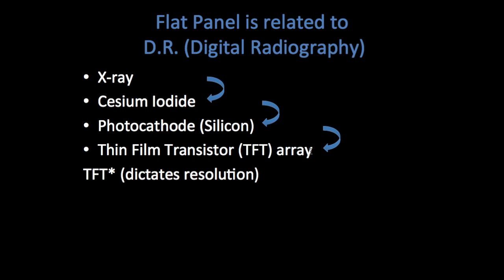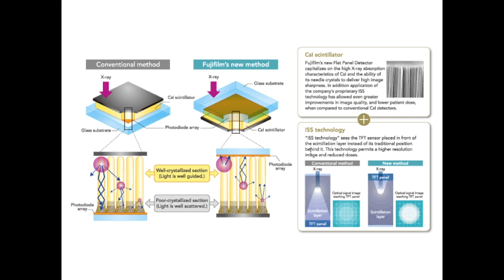Next, a photo cathode converts that light to electrons, and then the thin film transistor (TFT) array records the signal. For flat panel detectors, the TFT is the limiting factor that dictates resolution. In the conventional method, an x-ray enters the system, hits the cesium iodide scintillator shown in yellow, which converts it to light. That light is then converted to electrons and recorded into a TFT array shown in orange.